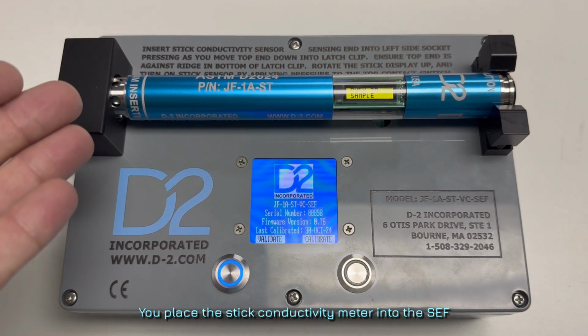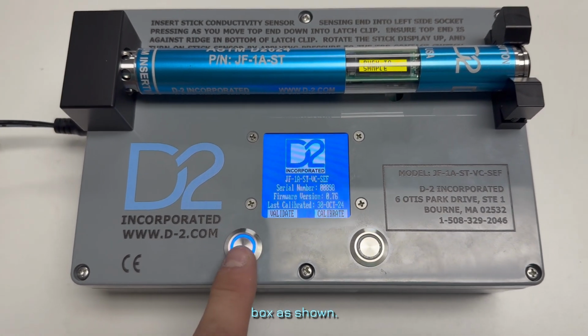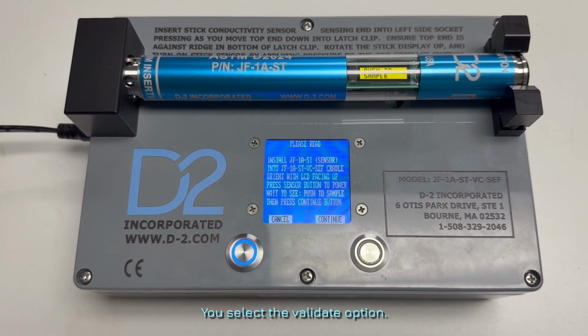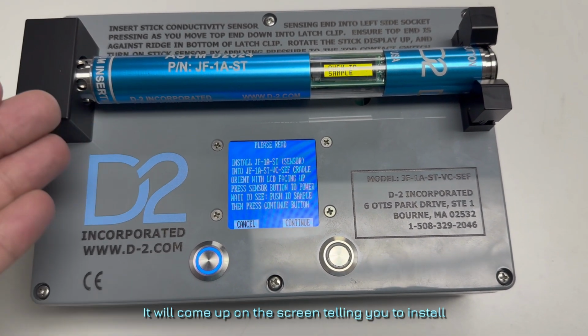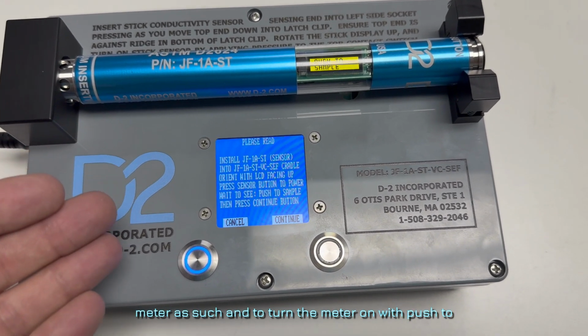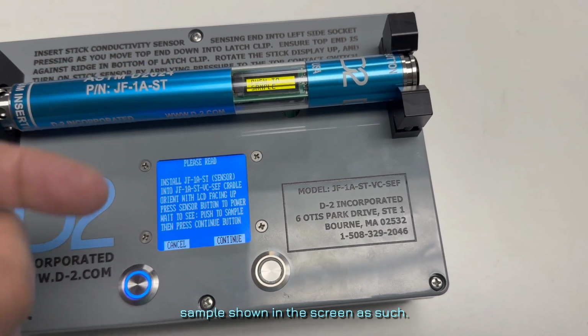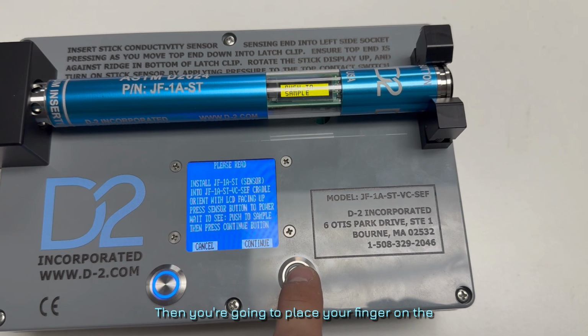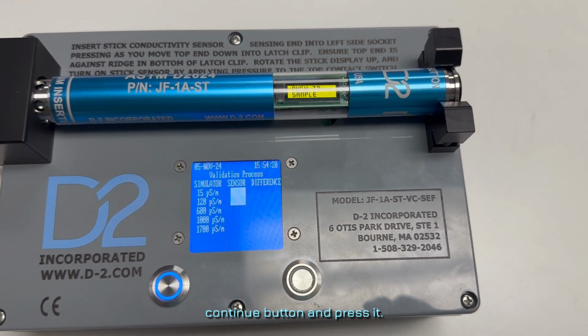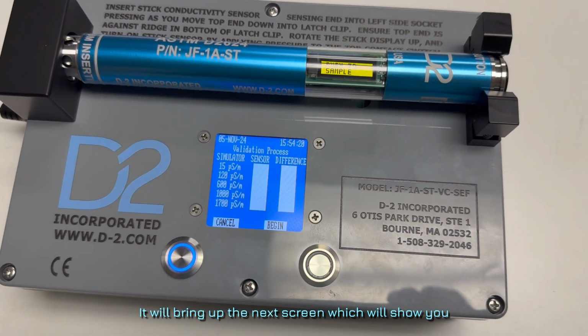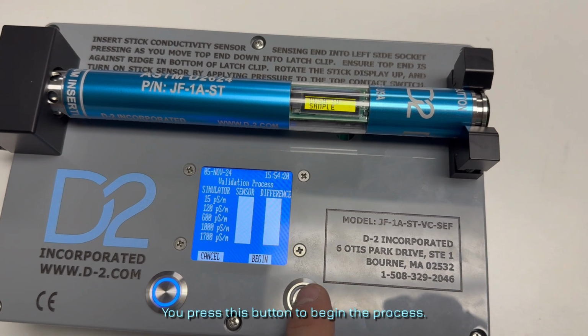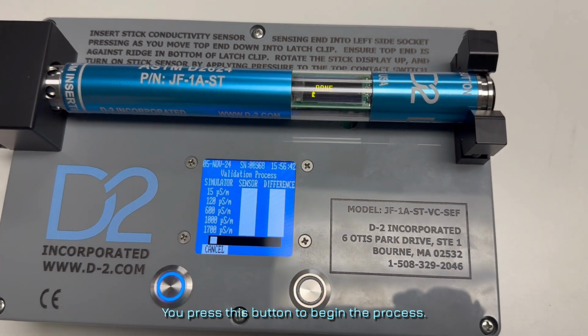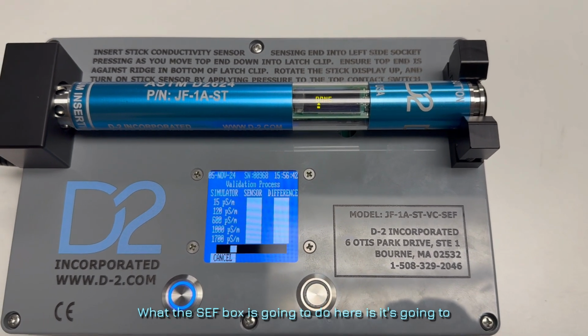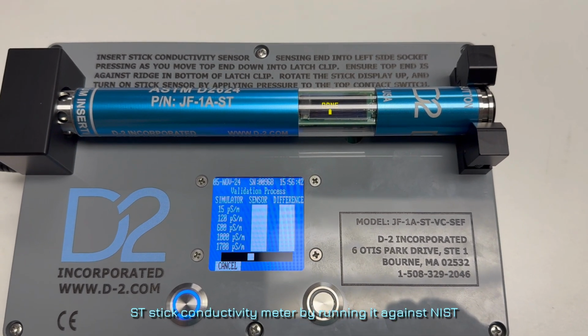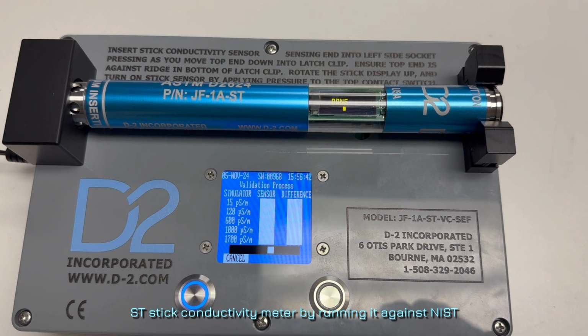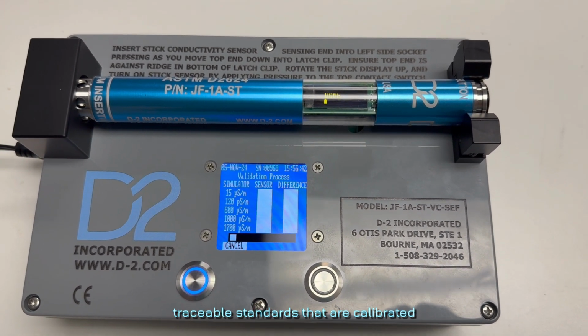You place the stick conductivity meter into the SEF box as shown. You select the validate option. It will come up on the screen telling you to install the JF1A ST stick conductivity meter as such, and to turn the meter on with push to sample shown in the screen as such. Then you're going to place your finger on the continue button and press it, which will bring up the next screen, which will show you the various samples it's going to take. You press this button to begin the process. And what the SEF box is going to do here is it's going to validate the calibration of the JF1A ST stick conductivity meter by running it against NIST traceable standards that are calibrated into the SEF box.